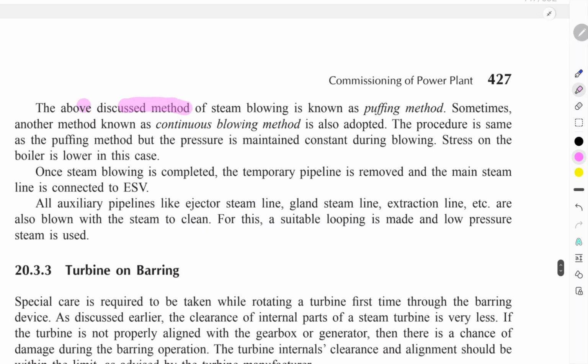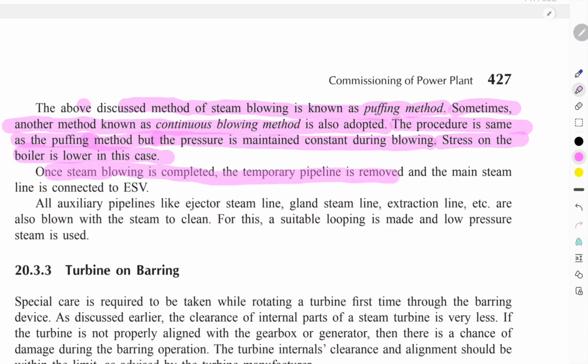The method discussed above is known as the puffing method. Sometimes another method, known as the continuous blowing method, is adopted. The procedure is the same as the puffing method, but the pressure is maintained constant during the blowing. The stress on the boiler is lower in this case. Once steam blowing is completed, the temporary pipeline is removed and the main steam line is connected to the ESV.